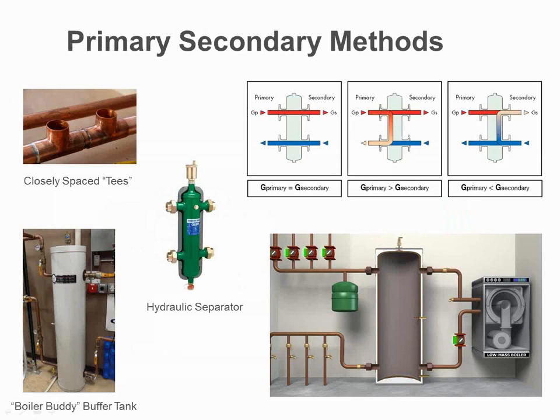Okay, here's another way. In the top left, we show you closely spaced T's. As you can see, there's probably a 1/2 inch in between those 2 T's. That's exactly what you want. Another method is a boiler buddy, as you see in the bottom left. If you look over to the right side, that's basically inside of it. It is nothing more than a buffer tank. It's a vessel of water. That's it. So we pipe in and out from the boiler to the tank, and we pipe out of the tank to the system and back around.